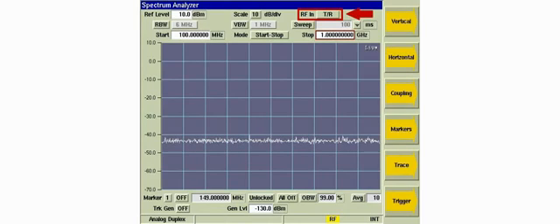The RF input is set to TR. This is important because in order to get an accurate measurement of the cable loss, we need to use the superior VSWR characteristics of the TR port.